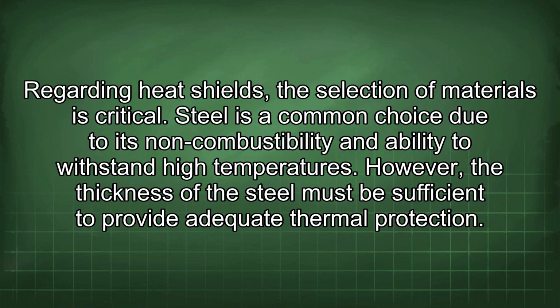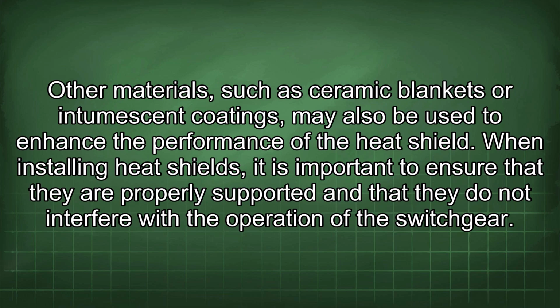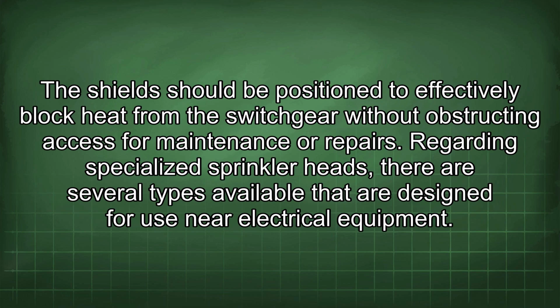Regarding heat shields, the selection of materials is critical. Steel is a common choice due to its non-combustibility and ability to withstand high temperatures. However, the thickness of the steel must be sufficient to provide adequate thermal protection. Other materials, such as ceramic blankets or intumescent coatings, may also be used to enhance the performance of the heat shield. When installing heat shields, it is important to ensure that they are properly supported and that they do not interfere with the operation of the switchgear. The shield should be positioned to effectively block heat from the switchgear without obstructing access for maintenance or repairs.